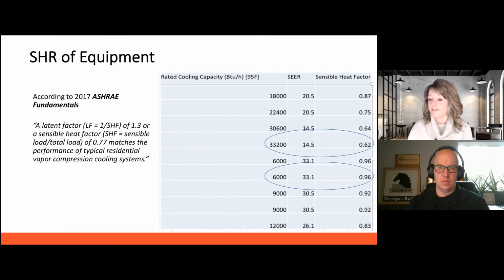But if we look down here at this half-ton mini split, we're at 33 SEER, which means it's really energy efficient, but 96% of the BTUs are going to sensible, and we've got 4% on the latent. And that's because, if you ever look at one of these, and you can't see my pen here, but I'm holding up a pen, the condensate line is about as big as a pen or a pencil. Very little water removal. It's very focused on just getting to that temperature, and it's not going to remove very much water. So we work with a lot of mechanical designers, HVAC contractors, builders. If they are using these high SEER systems, we want to make sure that there's for sure dedicated dehumidification included in the design of that system.